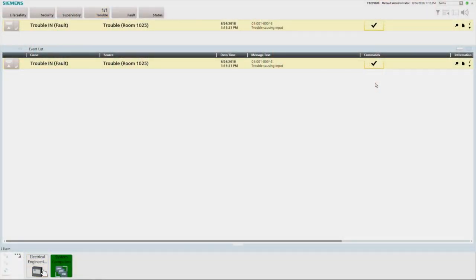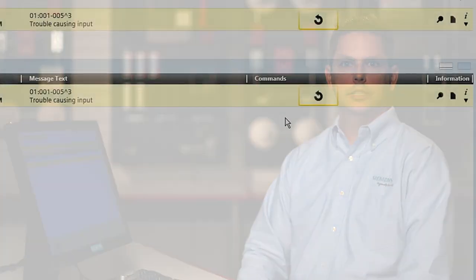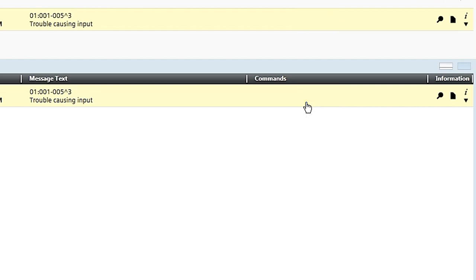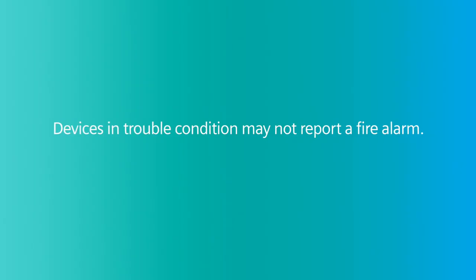A trouble is indicated in the summary bar by the yellow flashing trouble lamp and the yellow flashing fire panel icon in the node map. In addition, a yellow event will be displayed in the event list with a yellow flashing event icon, and the workstation audio indicator will sound. To acknowledge the trouble signal, press the acknowledge button in the commands column. The workstation audio indicator will be silenced and the trouble event lamp, event icon, and source fire panel icon will change from flashing to steady. When the trouble condition has been cleared, you may need to reset the panel to restore normal standby by pressing the reset button. Note that devices in a trouble condition may not report a fire alarm. Thank you for watching this presentation. We hope this video will help your team effectively operate your Cerberus DMS system. Please feel free to reach out to us with your future fire and life safety needs.